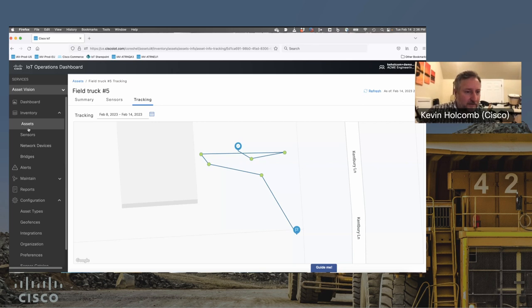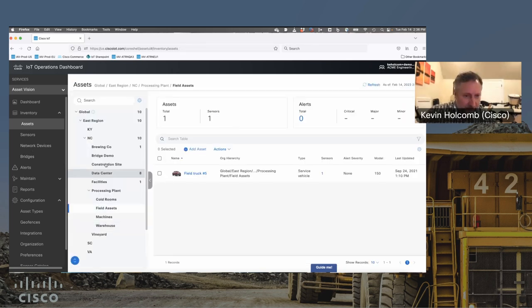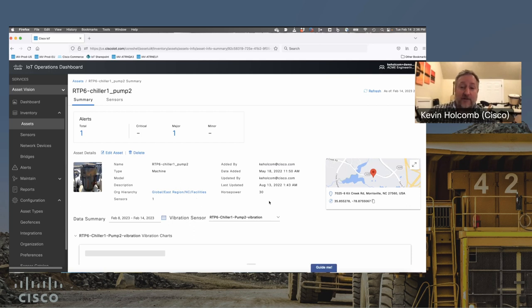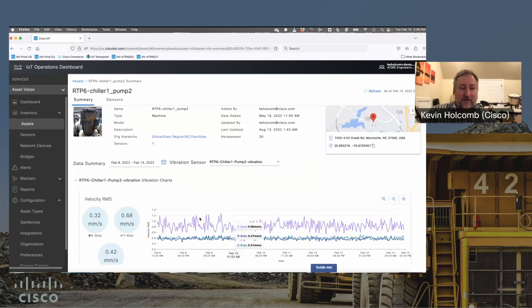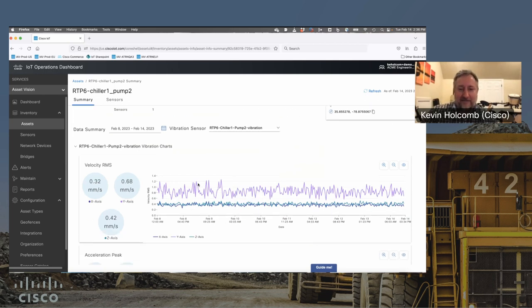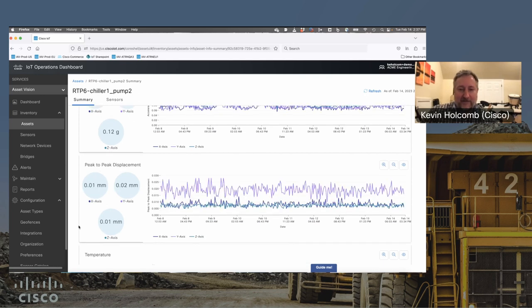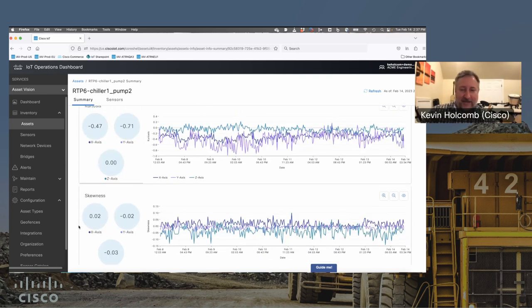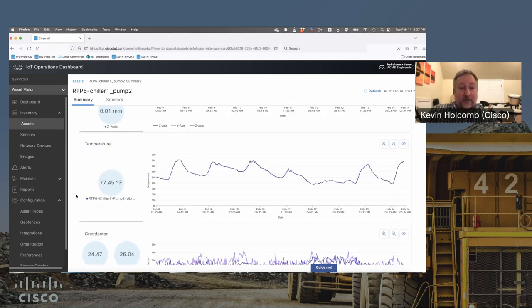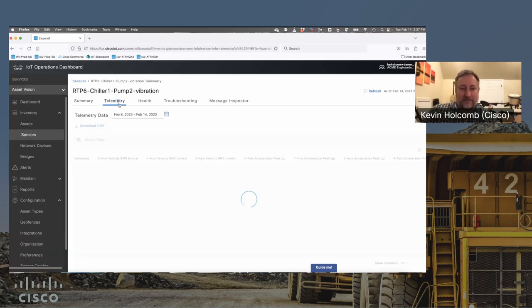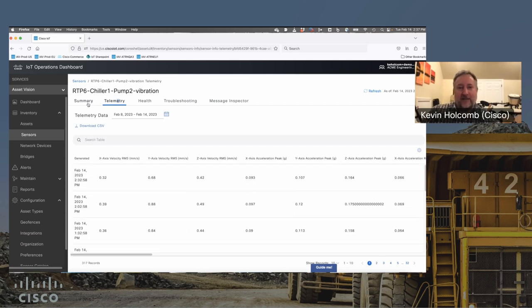For the vibration sensor, here's the data that comes off of it. On the roof of a Cisco building we have a chiller pump with a vibration sensor installed for almost a year. You can see velocity RMS, acceleration peak per axis across all axes, and the statistical derivations — crest factor, kurtosis, skewness, and deviation. You can also export that data in tabular form as a CSV, useful for sharing with someone who isn't an Asset Vision user.